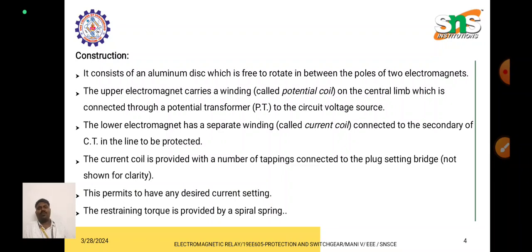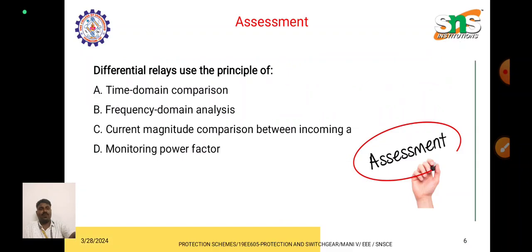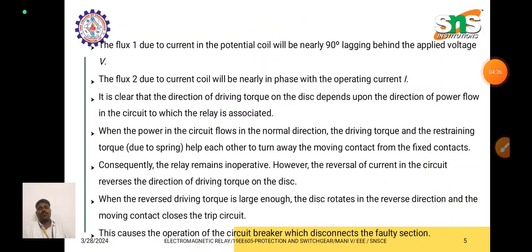The upper electromagnet carries a winding called the potential coil, or voltage coil, or pressure coil. The lower electromagnet has a separate winding connected across the CT, with a number of tappings and a plug setting multiplier, which are used to adjust the voltage and the current value. The interaction of these two fluxes across the aluminum disc produces a driving torque. The restraining torque is produced by the spring.